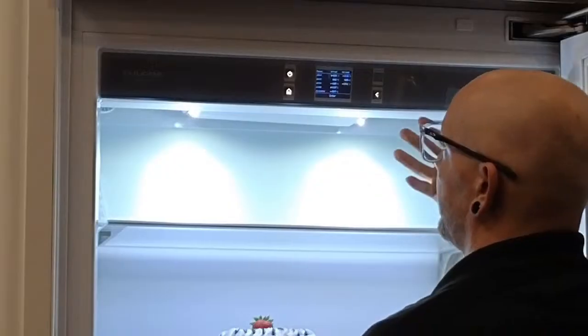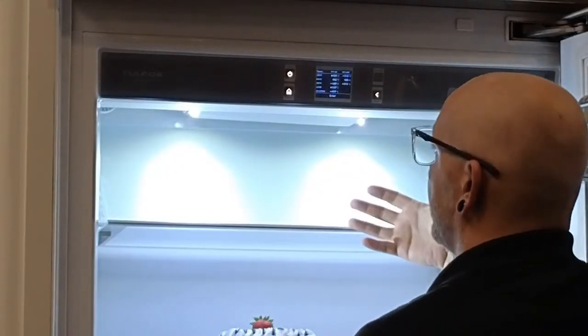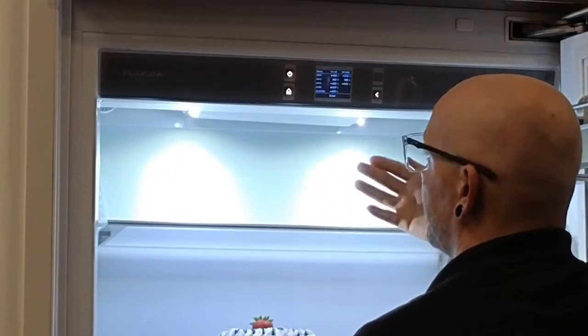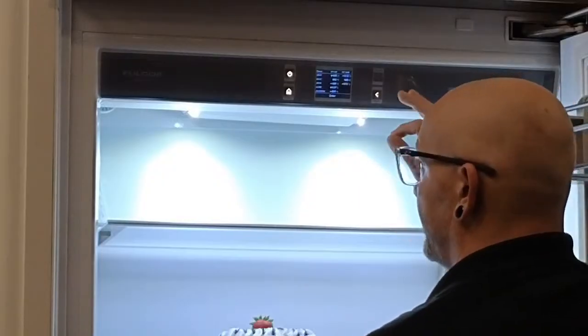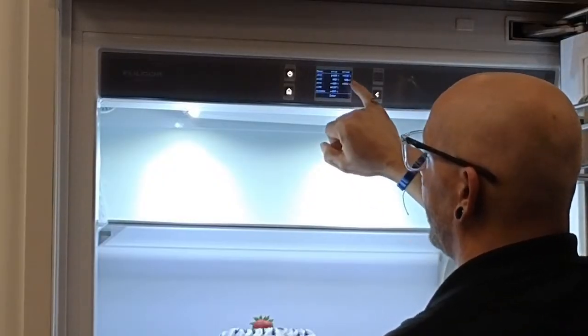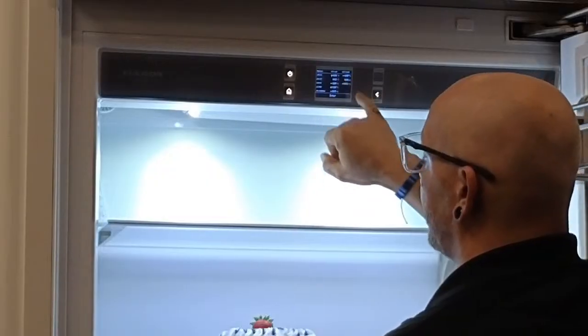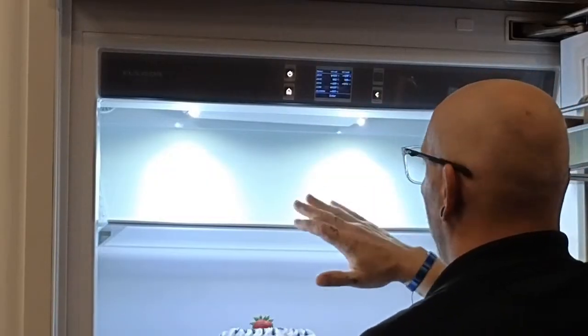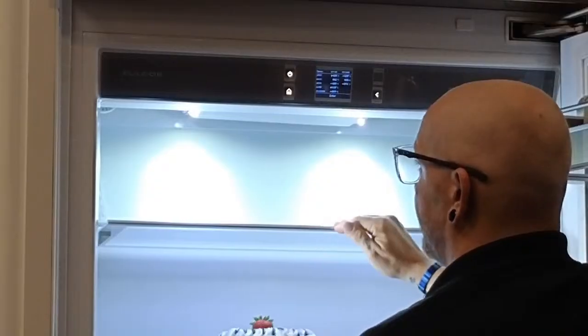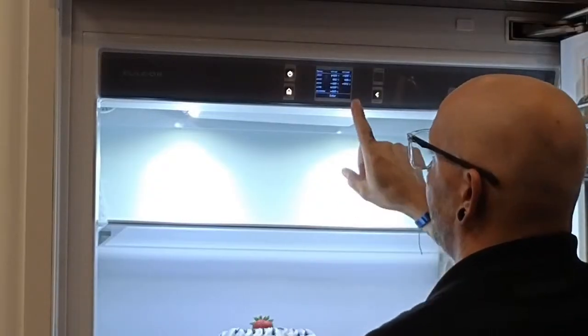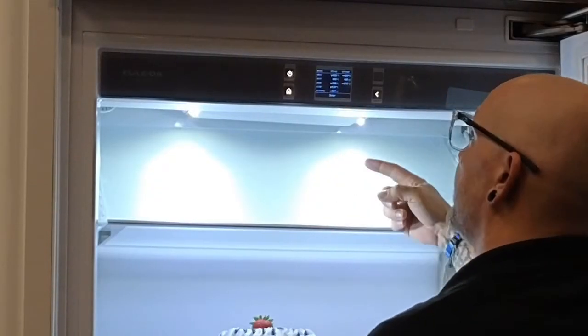This will tell a refrigeration technician a lot about what's going on inside of the machine just off of the sensor readings alone. And just as a little tidbit, if you see a -40 readout anywhere you would normally have a sensor, -40 is an automatic open sensor. It's just a bad sensor. It must be replaced. So if you push enter at this point, you're going to go into service mode.